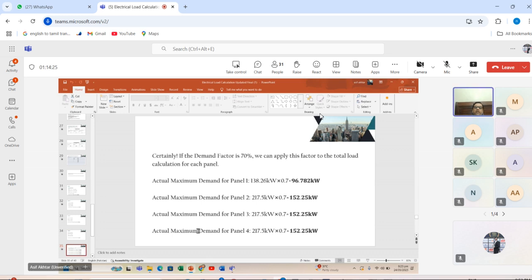Now suppose the demand factor is 70%. We can apply this factor to the total load calculation for each panel. The actual maximum demand for panel 1 is 138.26 multiplied by the demand factor, and we get the figure 96.782 kilowatt. In this way, we will do all the calculations for panel 1, panel 2, panel 3, and panel 4.